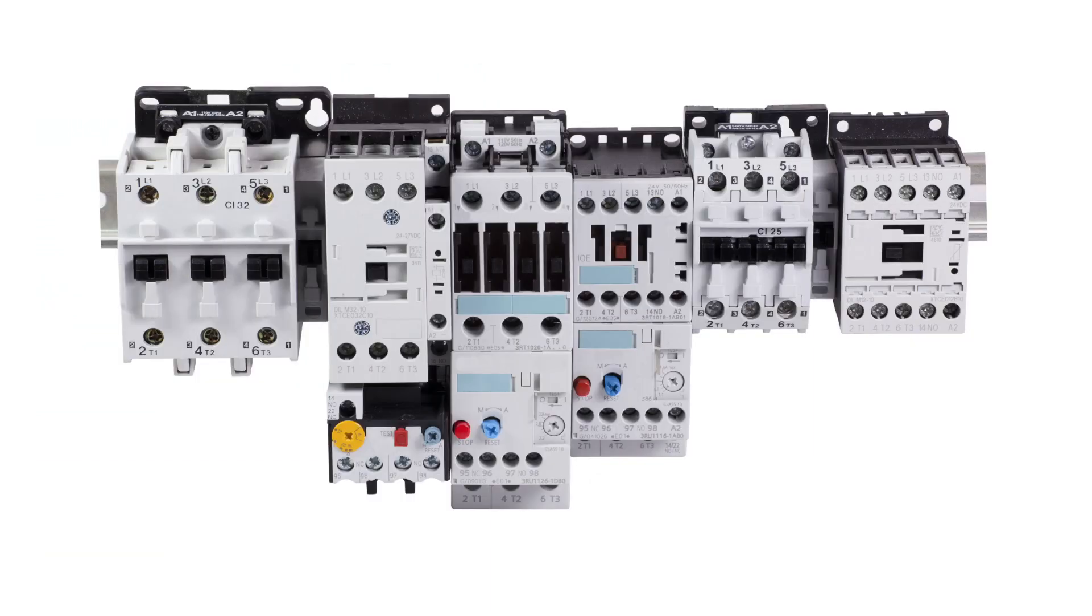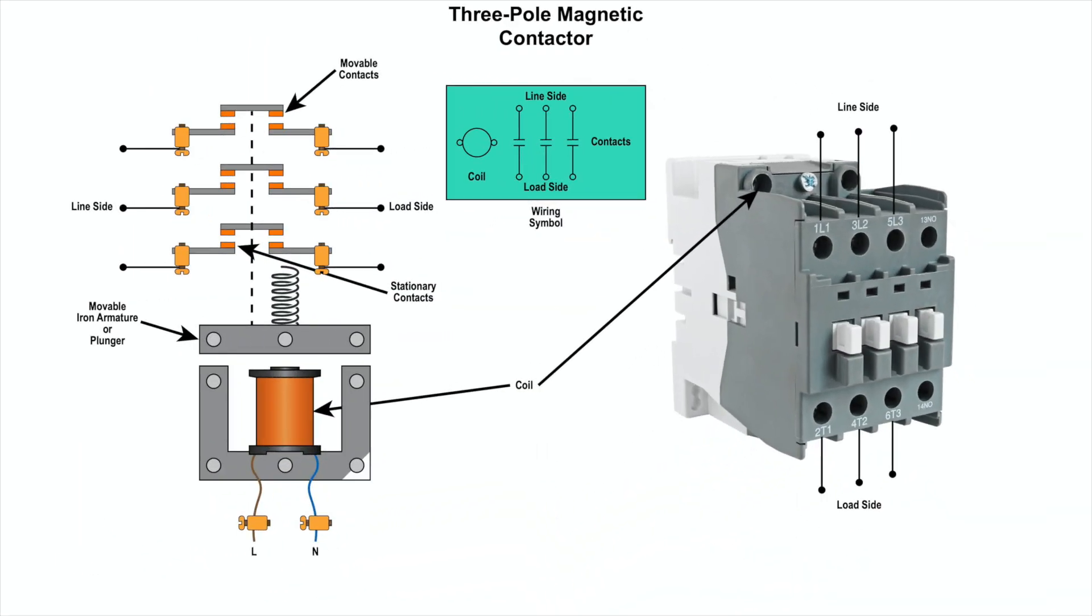A magnetic contactor is a magnetically actuated device for repeatedly establishing or interrupting an electric power circuit. The contactor is similar in operation to the relay. The difference between the two is that the contactor is used in applications with higher current carrying capacity, whereas the relay is used for lower current applications.